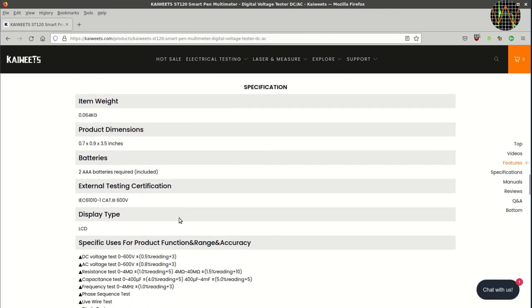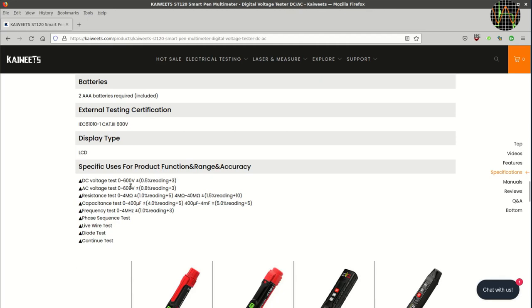A quick look at the specs. Rated for CAT3 work up to 600V which is impressive. That would cover all domestic installations and some work on three-phase industrial plants and lighting circuits. Not setting the world on fire as far as accuracy is concerned, but certainly in line with what you would expect these days from a meter for electrical installations.